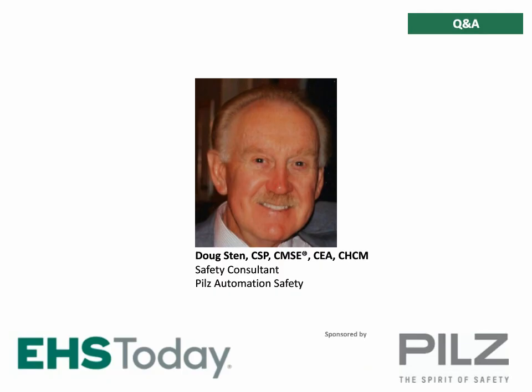Well, they don't really. The one thing you've got to be concerned about with light curtains and scanners is the floor space. You can use scanners, which is fine. You can use light curtains both vertically and horizontally. Now, if you're using light curtains horizontally, they have to be at least 4 feet long, so that people standing can't jump over them. And if you have them installed vertically, you've got to make sure that you do safe distance calculations, that the light curtains are back far enough that if I break the light curtain, all hazardous motion and movement will stop or cease.